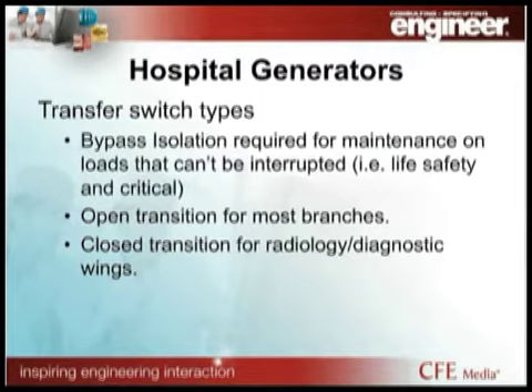Transfer switches also require maintenance. This is, again, codified, written down, and one of the ways that traditional engineers have designed this is with a bypass isolation feature on the essential portions of the transfer switch. So most transfer switches to date are open transition, and recently we've moved towards closed transition for our computer-intensive radiology department's diagnostic wings.